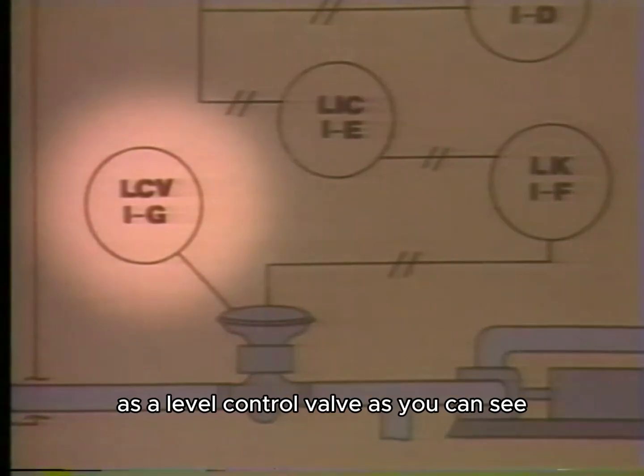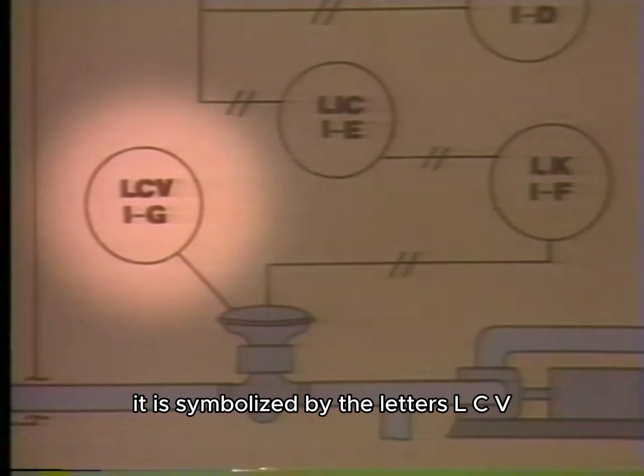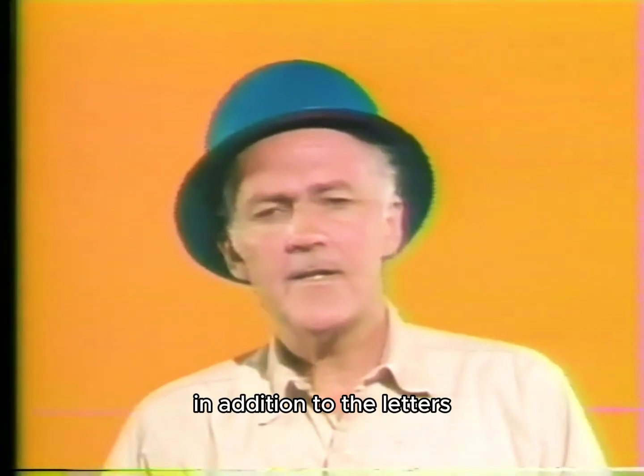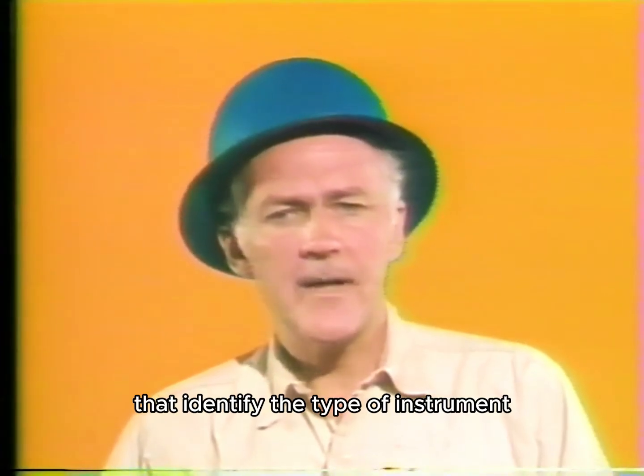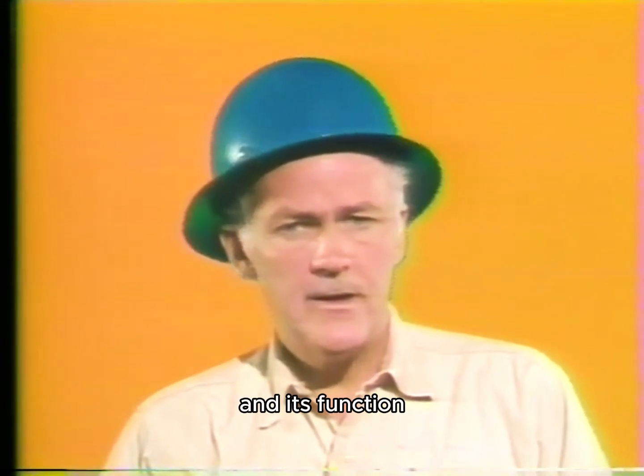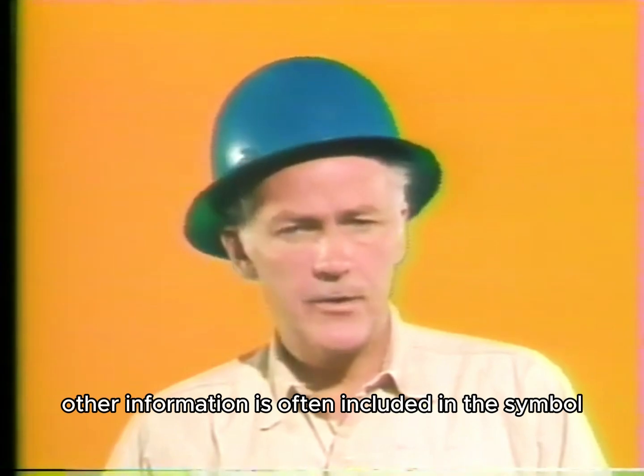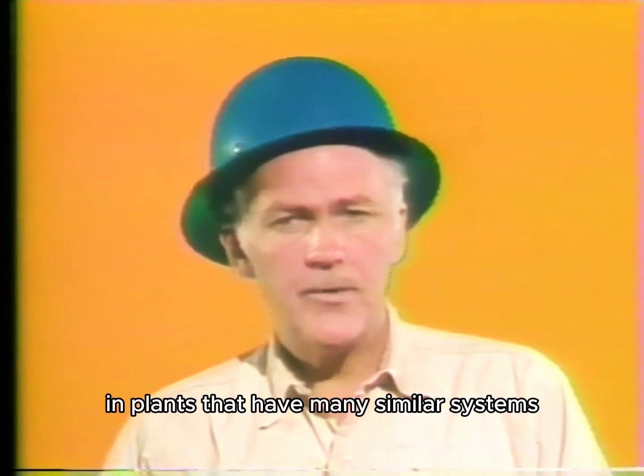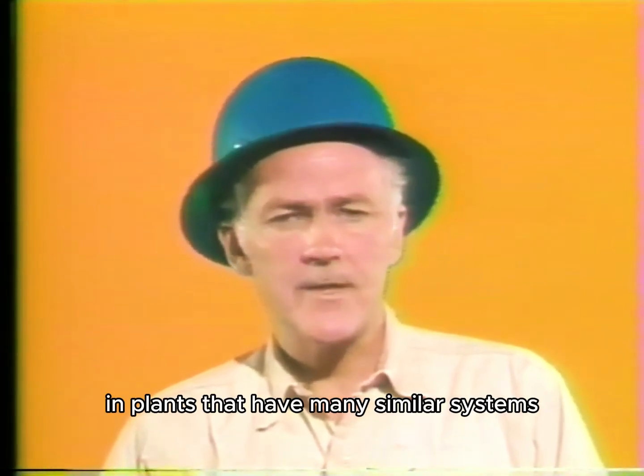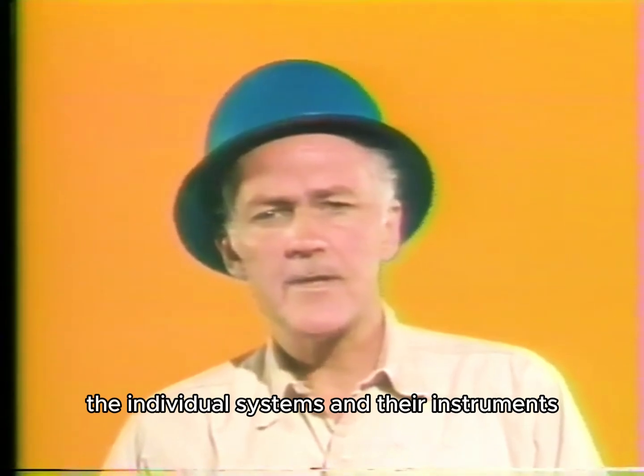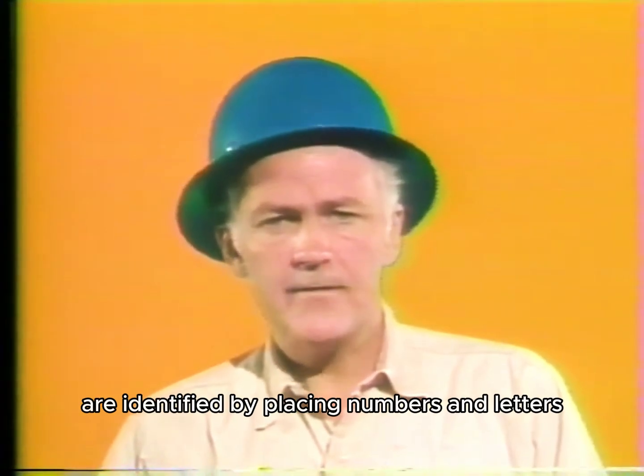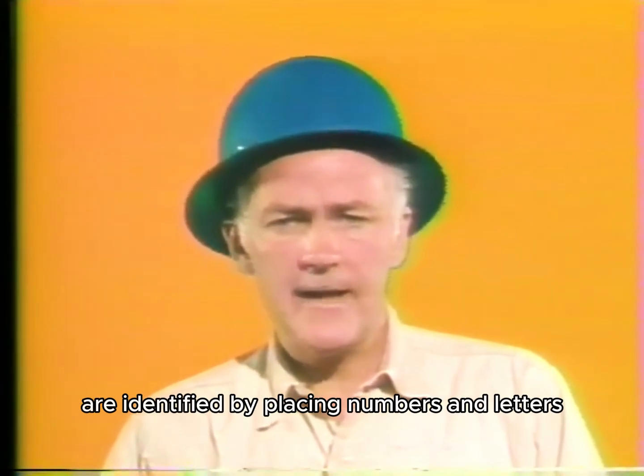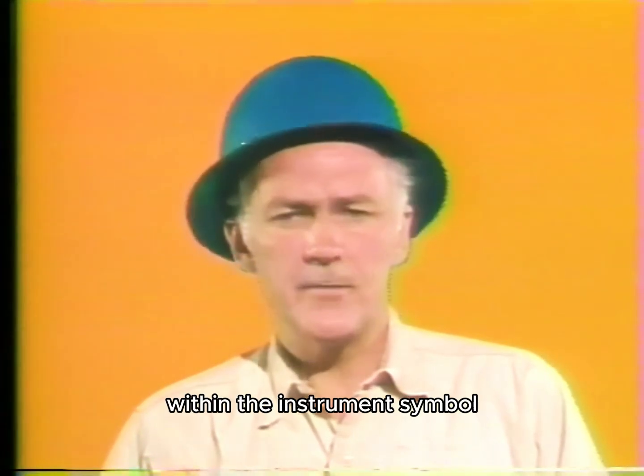As you can see, it is symbolized by the letters LCV. In addition to the letters that identify the type of instrument and its function, other information is often included in the symbol. In plants that have many similar systems, the individual systems and their instruments are identified by placing numbers and letters within the instrument symbol.